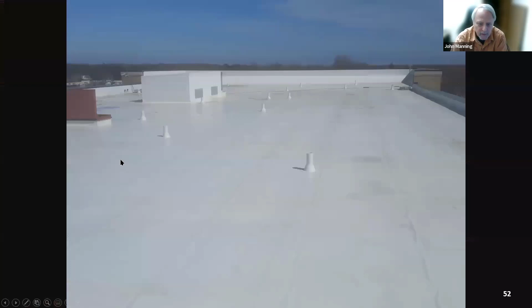If you can scan one more page. That is the system, that's the Samsung VRF, this is only a heat pump. As you can see, there's an unconnected port on the refrigerant lines. But these 4 units are taking the place of everything that would otherwise be up on the rooftop. Everybody here is probably a geothermal-experienced person who understands that, so it's probably not impressive to you. But in this situation, these 4 16-ton units are each connected to about 20 different air handlers throughout the building. Each air handler, essentially each thermostat in each unit, contacts this unit, and this unit will use its variable speed compressor and send refrigerant to whichever air handler is calling.